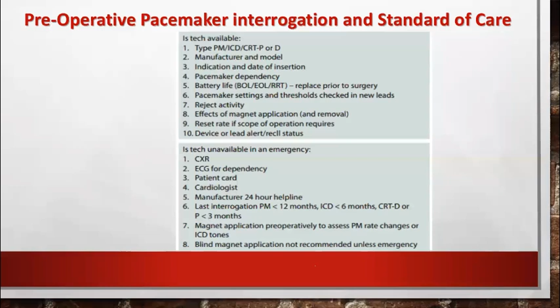Last interrogation: this is very important. For a pacemaker, less than 12 months; ICD, less than 6 months; CRT-D, less than 3 months, because battery drainage is very important in these patients. If the patient has a CRT-D, or a D or P device, the battery drains faster, so it has to be checked. Magnet application preoperatively is used to assess pacemaker rate changes or ICD tones. Blind magnet application is not recommended unless it is an emergency.